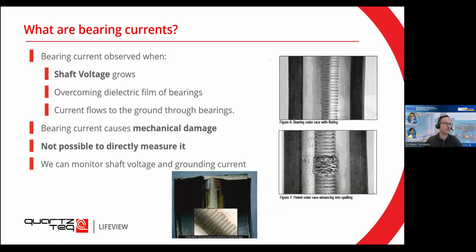So as you can see on the pictures on the right and the bottom, you have this kind of fluting, and essentially you're just making mechanical grooves, or even big holes like this. And this can lead to some really catastrophic failures if your bearings essentially stop working mechanically. The issue here is that it's not possible to directly measure it through the discharges, but what we can do is we can monitor the shaft voltage and also the grounding current.